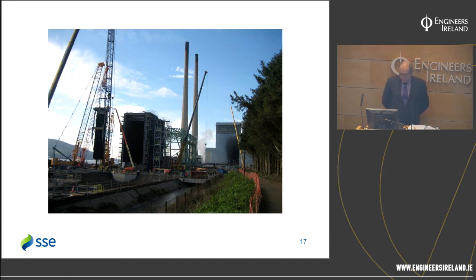We had a problem subsequently in plant operation about 18 months in with the HRSG. It was quite an unusual problem in that one of the flue gas thermocouples was, due to a design issue, located in the wrong place. It was located too close to one of the tube banks. So when the HRSG heated up, the tube bank shifted sideways and began to rub against the thermocouple pocket, and in the end, the thermocouple pocket rubbed a hole in the tube bank. So we had a tube leak about 18 months into operation, which is quite unusual. But the reason for that was readily identified and fixed.